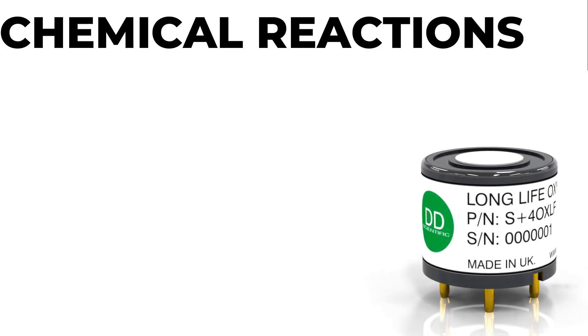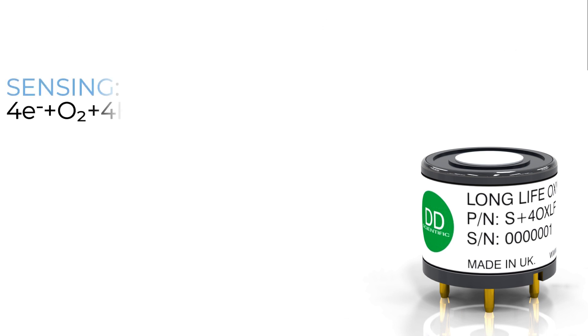So in summary, at the sensing electrode we have a chemical reaction called reduction whereby oxygen is combined with protons and electrons to form water. At the counter electrode water is hydrolyzed to produce oxygen, protons and electrons. This is the opposite reaction to what is happening at the sensing electrode.